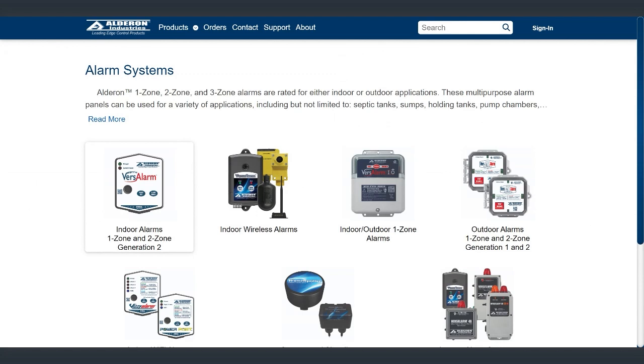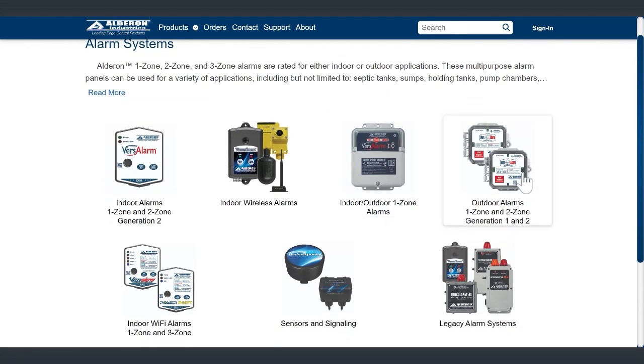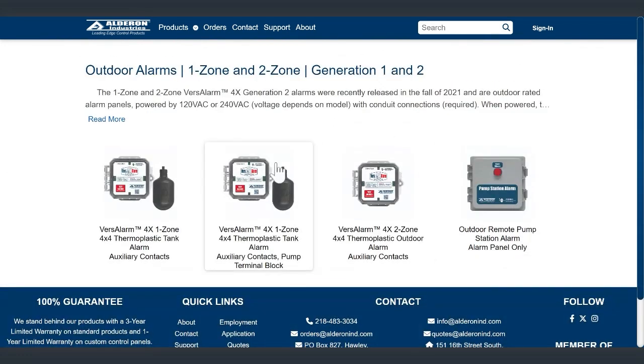We have our indoor-outdoor 1 zone alarm, and that looks like this. There's terminals in here for incoming power. This is voltage specific, it's 120 or 230. And you have your float connection, and then also auxiliary alarm contacts. So if you wanted to tie it into a building automation system, you could do that as well. And then we have our outdoor alarms, and we have a couple options with those. Pretty much all of them have auxiliary contacts built in, and then you can get them with floats or without floats. And that one we have 1 zone or 2 zone available. And this is all enclosed.